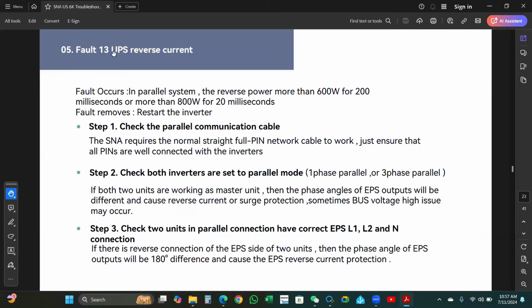Number 5, fault 13, UPS reverse current. The fault occurs in a parallel system when the reverse power is more than 600 watts for 200 milliseconds or 800 watts for 20 milliseconds. Fault removes on restarting the inverter. Step 1, check the parallel communication cable. You just have to make sure the normal straight full-pin network cable is working, and that all pins are well connected with the inverters.